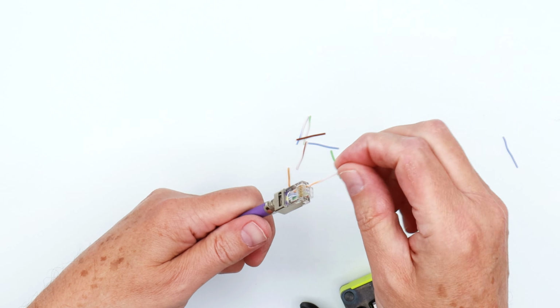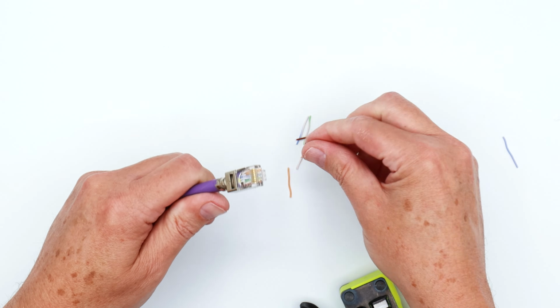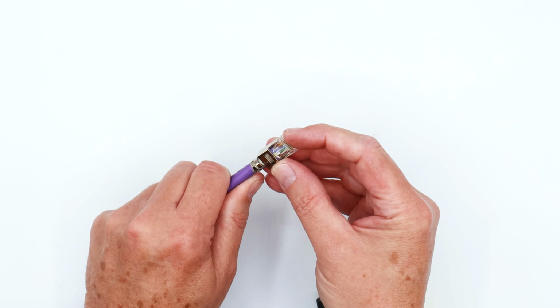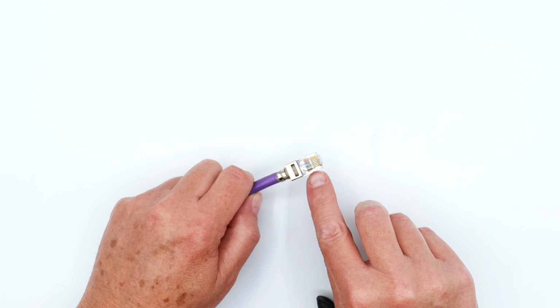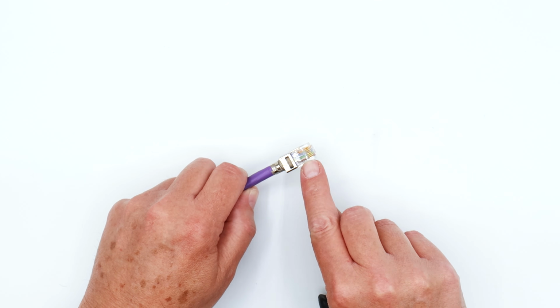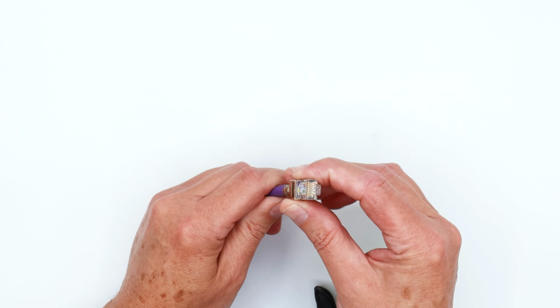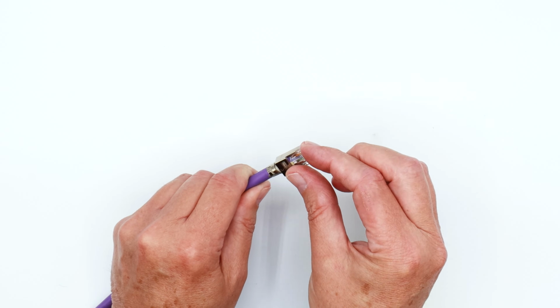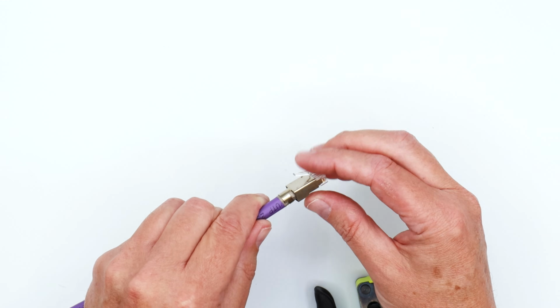You may have a little hanger on. It's just a little piece of plastic, that's all. It actually cut the conductor. So that's it. The cable's properly seated, so you have a half-inch distance. All your golden contacts are down. It's fully flush cut at the front, and it's ready to go ahead and plug in.